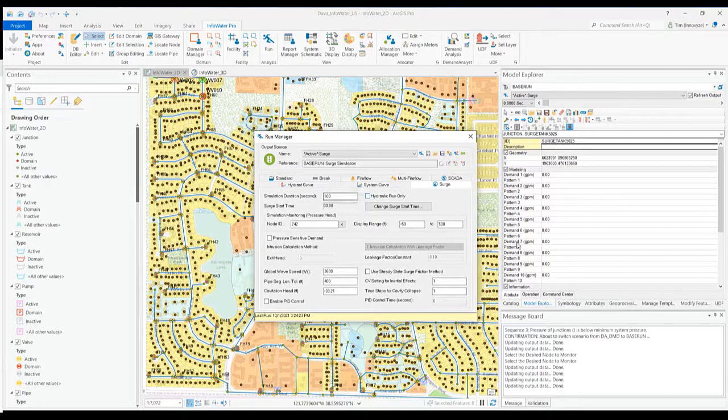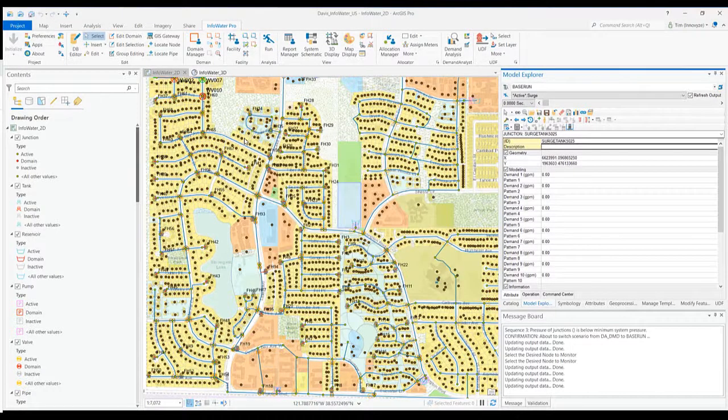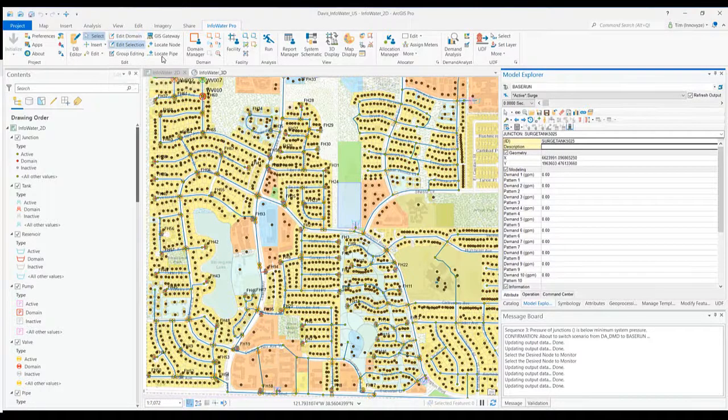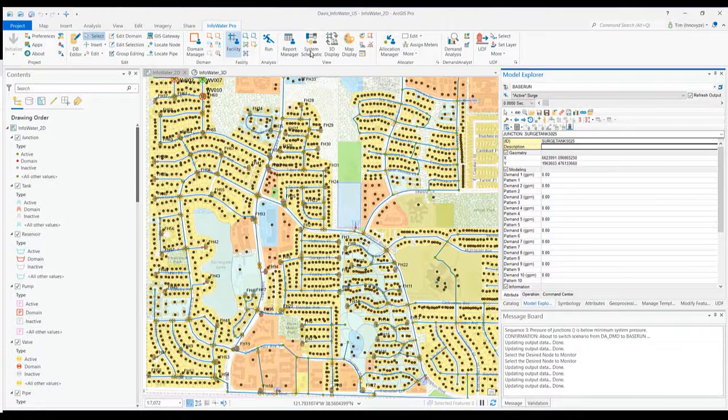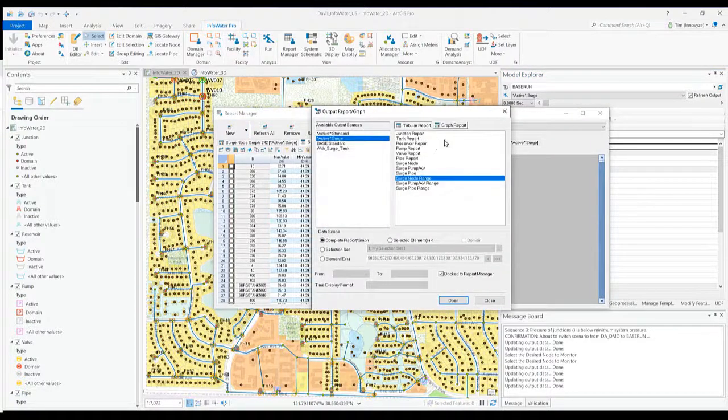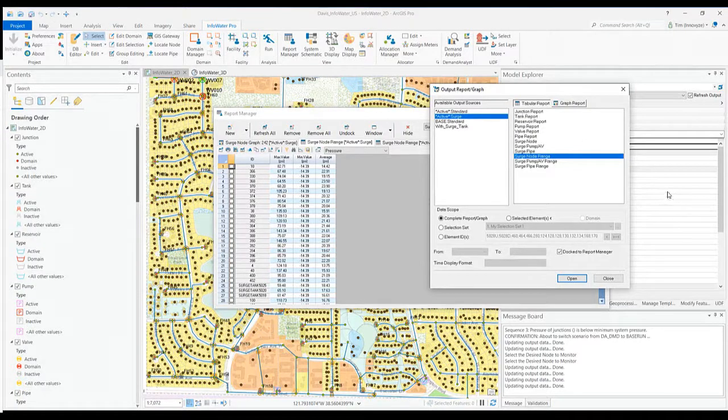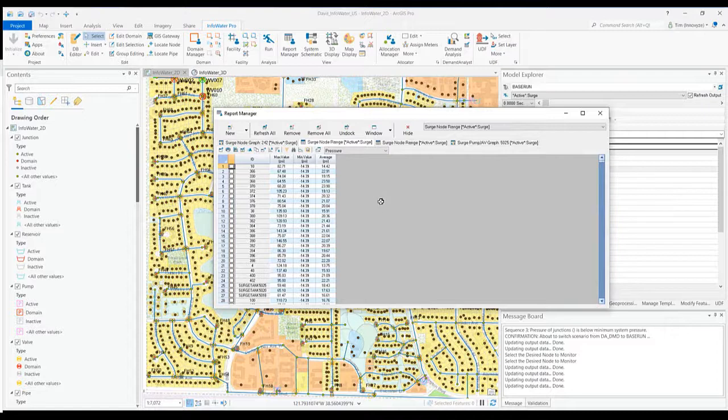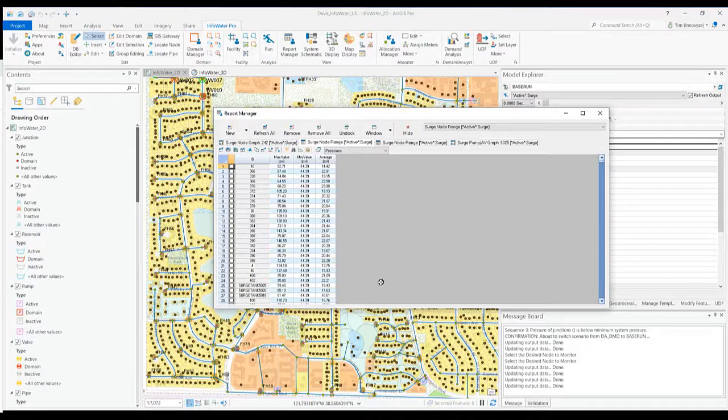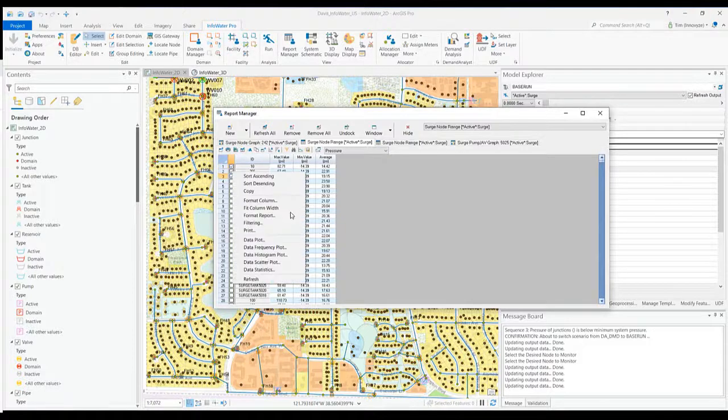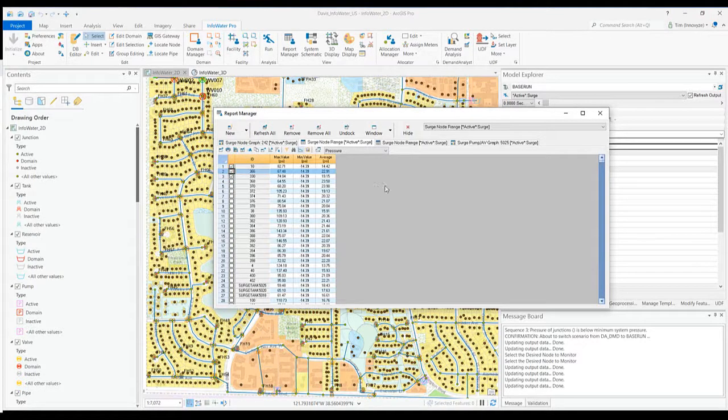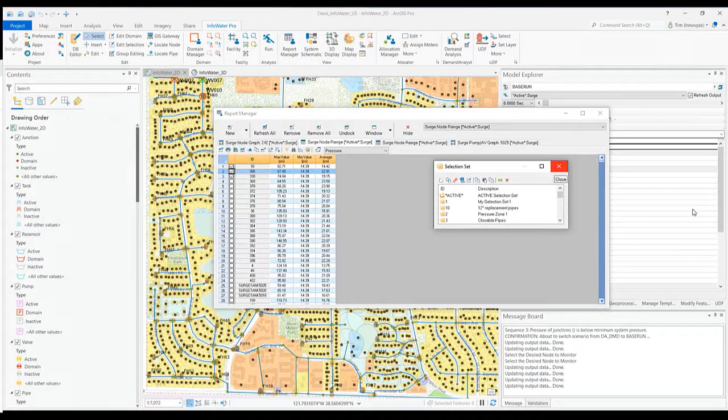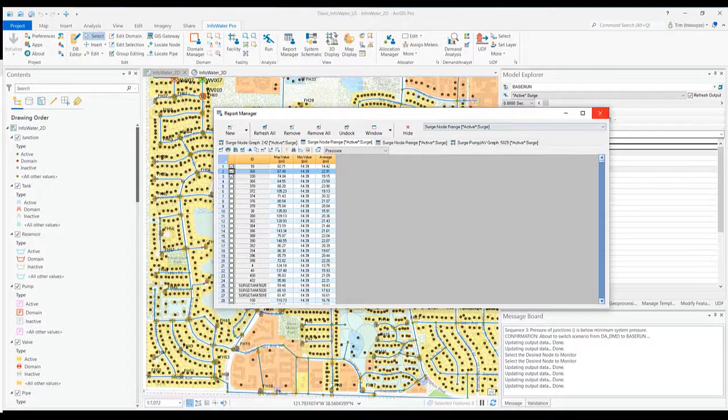Once you run your surge analysis, one quick way to identify areas where you might be having transient events is to go to the report manager and look at the surge node range. Anywhere you are seeing minimum values for pressure during your surge event that are below or at zero, those are areas where there could be cavitation, and you could easily select and add those for review.